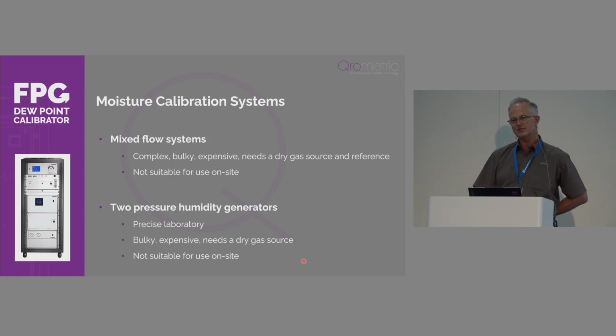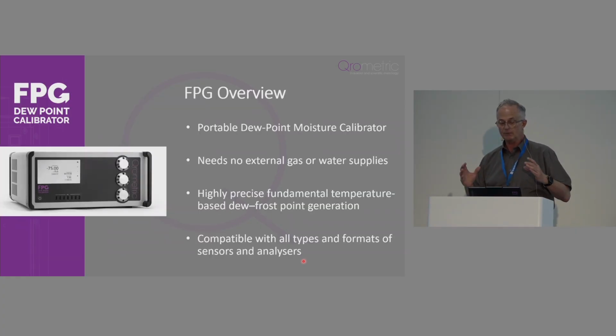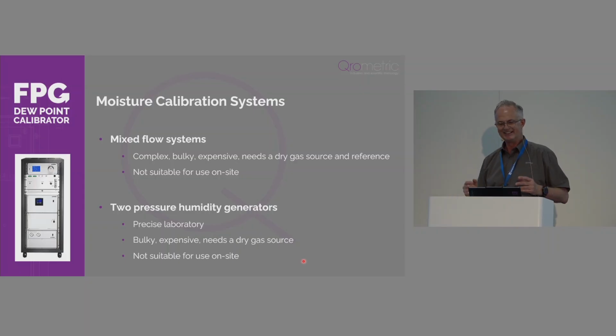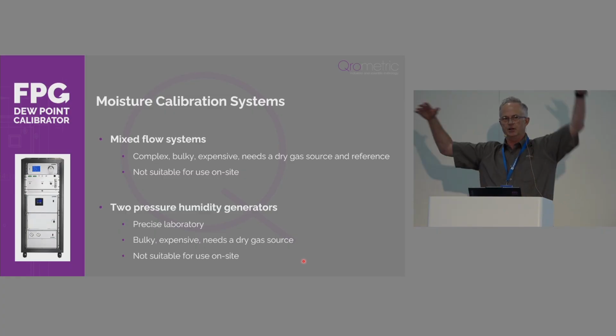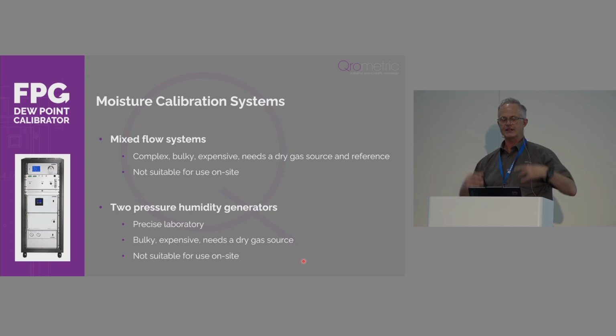Then we have moisture calibration systems such as the mixed flow. So we have a rack where we mix dry and wet gases to be able to calibrate the sensor. And then we have 2 pressure generators, which are laboratory-grade instruments, which are fabulously accurate. But both of these systems are big and large and need a compressed air supply, so not very practical for use on site.